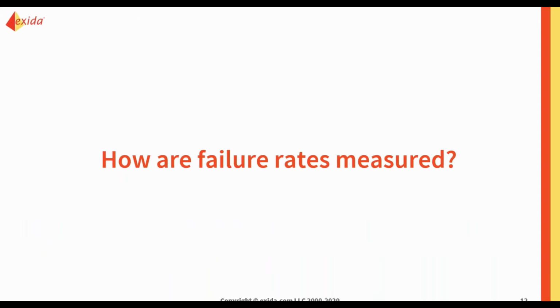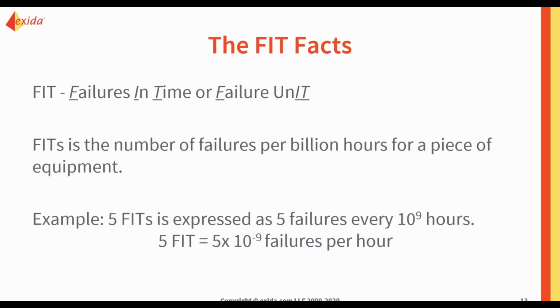So how are failure rates measured? Well, you might have heard of things before called a FIT. That's usually what we're dealing with when we talk about failure rates. A FIT could be described, I've heard both ways, and both ways are correct, as failures in time or failure units. But they both mean the exact same thing. It is the number of failures per billion hours for a piece of individual equipment.